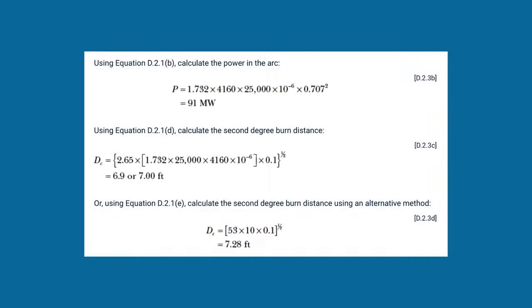So now, once I do the calculation for the arc flash, if that arc flash exceeds what that limited approach boundary is, then that becomes your new boundary and your new barricade. Okay, gotcha. So this is the overall limited approach boundary combined with the restricted approach boundary. Yeah, the limited is just to protect unqualified personnel from entering the area. When you're in the restricted, we consider that the same as you're going to be working on it, so there are no inadvertent movements within that area.